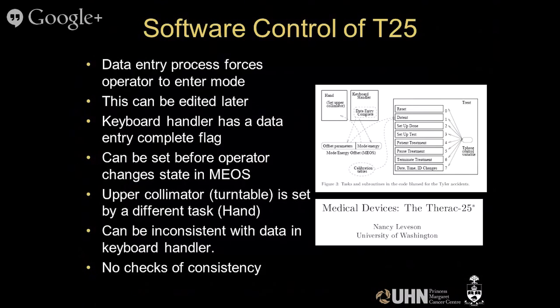So the software control of the Therac 25 was done, as we've learned, by computer. This diagram over here on the right explains a little bit about how the computer control works. It's a very complicated diagram, and I have to confess I don't exactly understand it completely. But essentially, my understanding is that there's a certain data entry which forces the operator to enter a mode. Now, this mode could then be edited later. Then there was a keyboard handler that had a data entry complete flag, a flag that says, "Yep, all the data is entered." When this is set, it changes the state in a part of the software called the MEOS. Then the turntable is set by a different task, a hand task, as opposed to this MEOS task. And what happened was that the software controller didn't verify that the MEOS and the hand task were consistent.